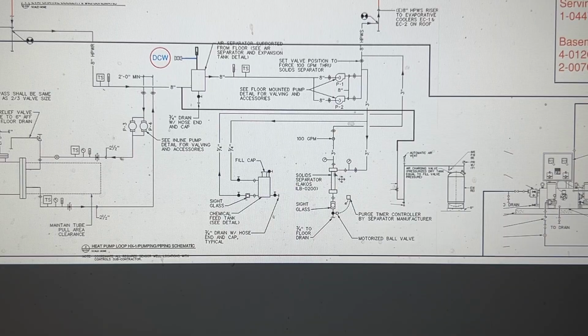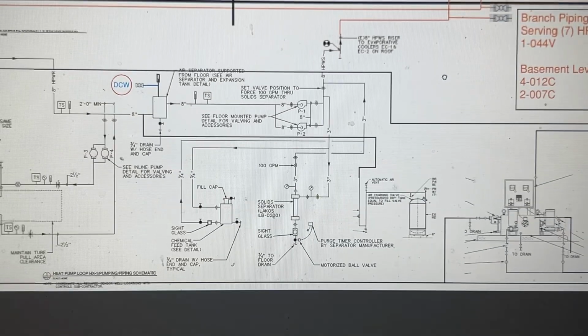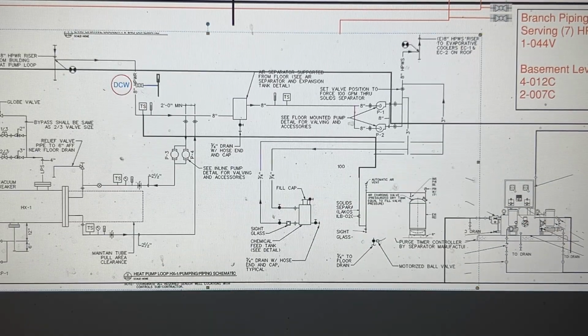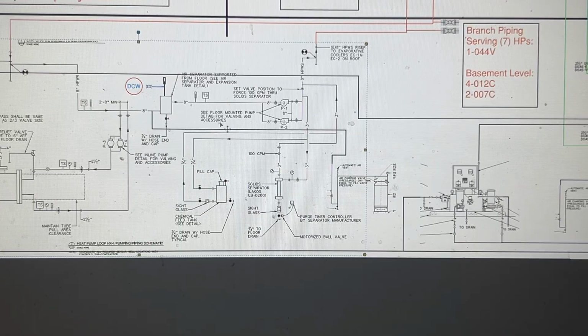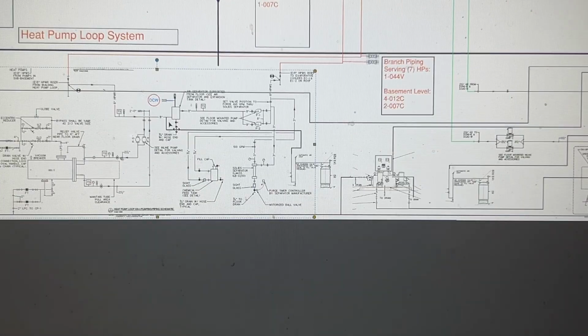There is a solid separator, which is pretty typical for a heat pump loop. It pretty much is an extra layer of protection. It's a bag filter that'll catch anything in the system to try to protect the equipment long term. Expansion tank acts as the bladder for the system.